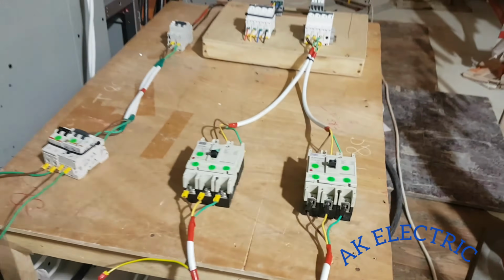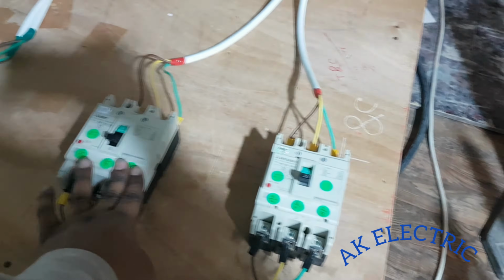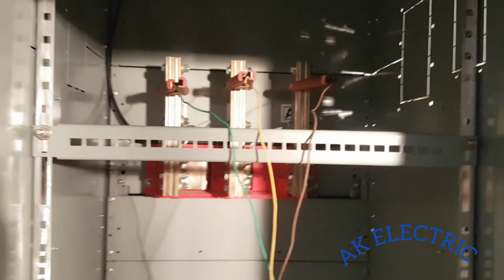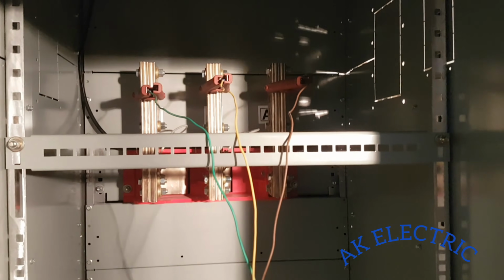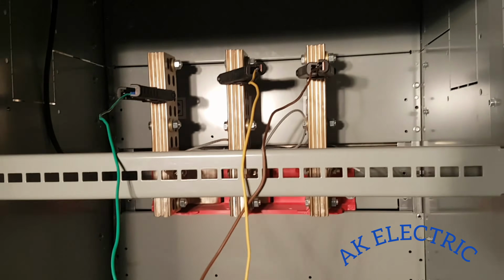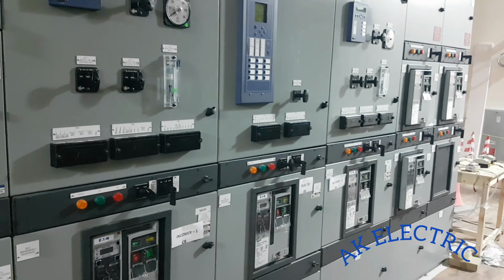Before that I will show you this connection. This supply will be connected to incomer 1. Here you see our switchgear backside. We connected the incoming supply, that is 380 volt. This is how we connected, and this is the bus tie. Same like this, for incomer 2 also we connected. This is incomer 1 we connected. This is our switchgear, and for this switchgear we are going to test the ATS function now.